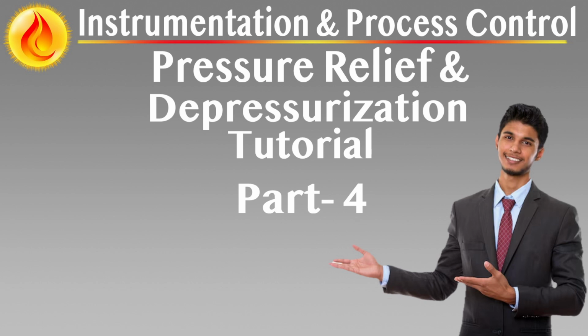Ignition control and operation. Ignition must be manually initiated from a safe location, typically at grade level, with visual line of sight to the flare tip to confirm pilot light up. The system must be capable of reliably igniting the pilots under design wind conditions and varying fuel gas compositions. The ignition circuit must deliver a stoichiometric air-fuel mixture at the ignition point. This requires carefully designed restriction orifices, accurate air and gas supply pressure control, and proper mixing to produce a stable flame front.